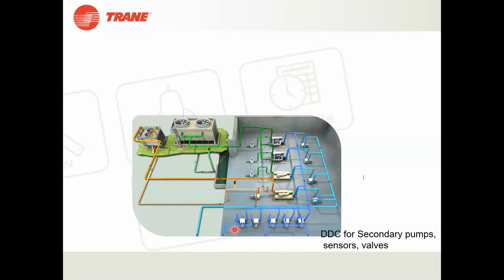So to automate this, what the pump vendor, the manufacturer of the pump, does is put PLCs along with the pumps. These PLCs get all the data, which can be integrated with the building BMS system. But the building BMS system has limitations, it can only monitor or do on-off, these two actions only. It cannot control the system, it cannot control these pumps, chillers, or cooling towers. Controlling, regulating, modulating, nothing is possible. So again your problem is not getting solved.